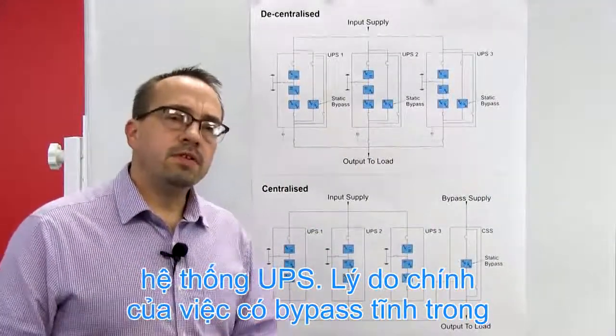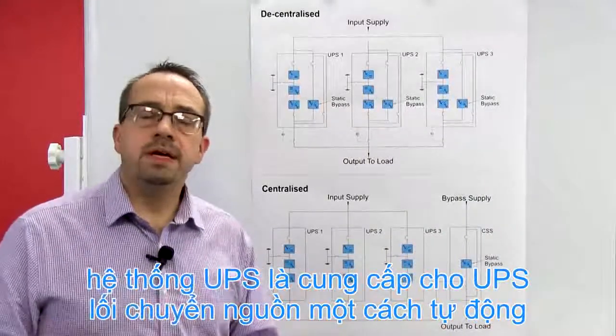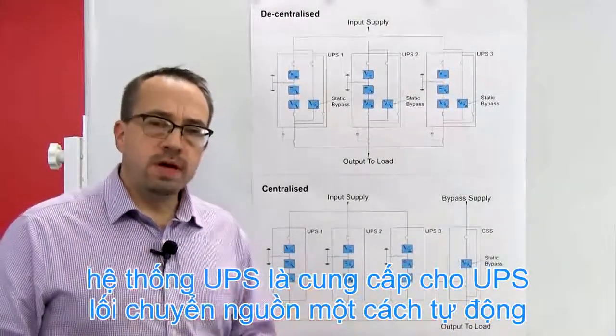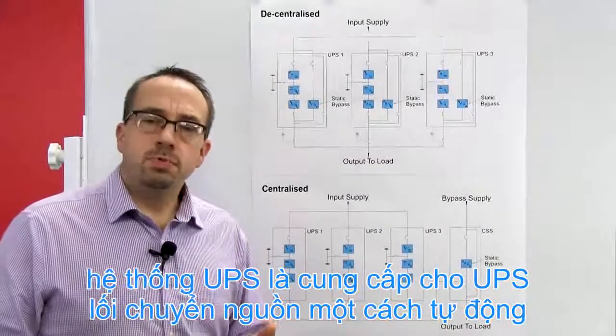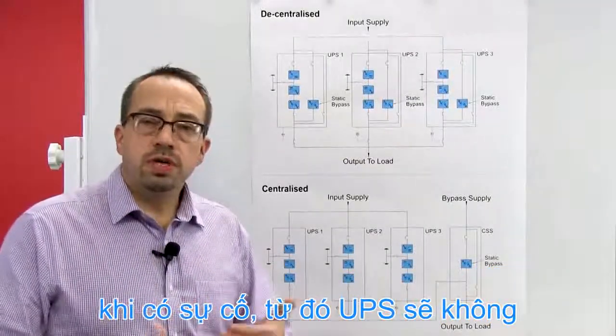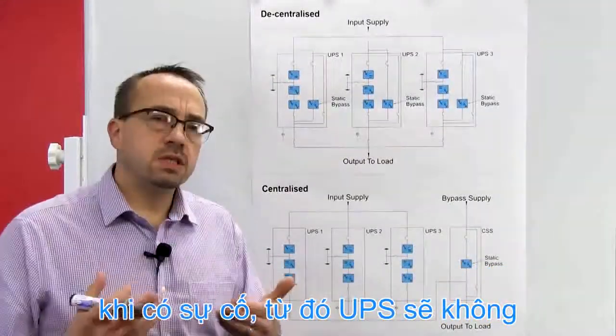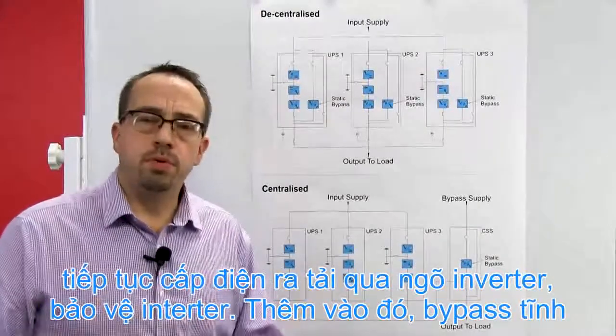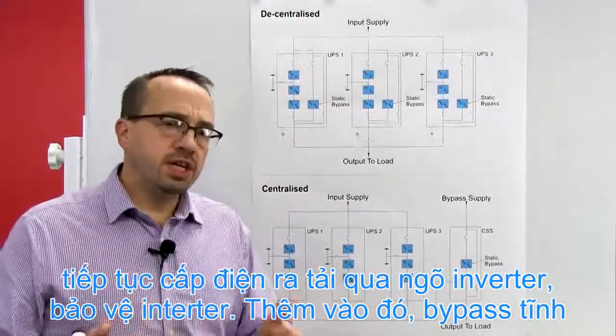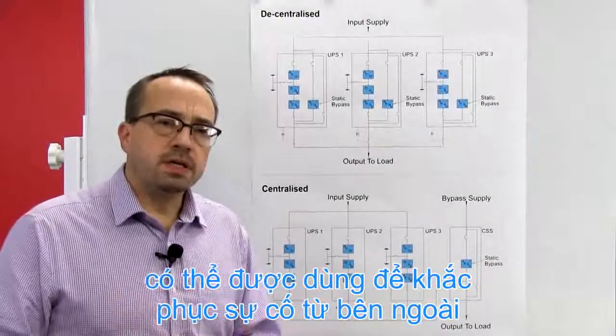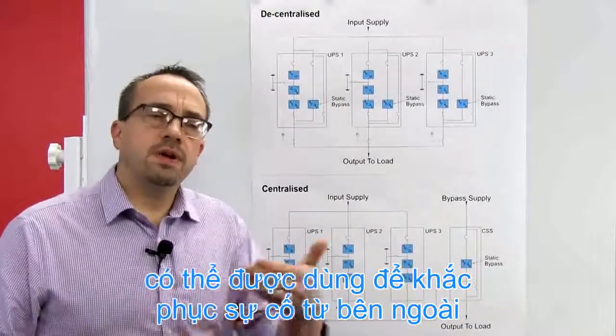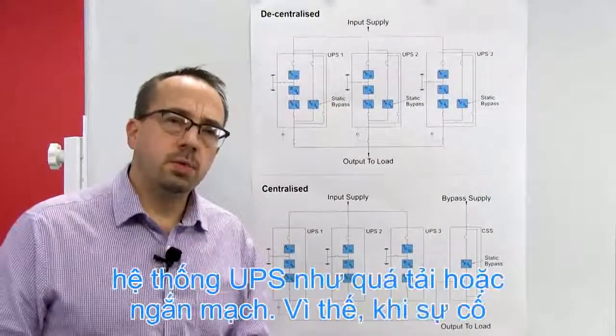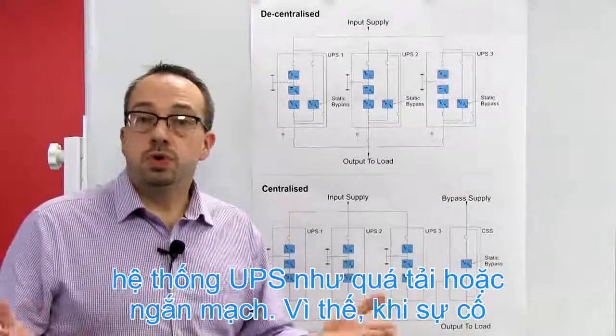Now the primary reason to have a static bypass within the UPS system is to provide the UPS system with an automated route of power around itself should an issue arise within the UPS, and hence the UPS can no longer adequately support the critical load. In addition to this, the static bypass can also be utilised in order to clear issues on the outgoing side of the UPS, such as overloads or short circuits.